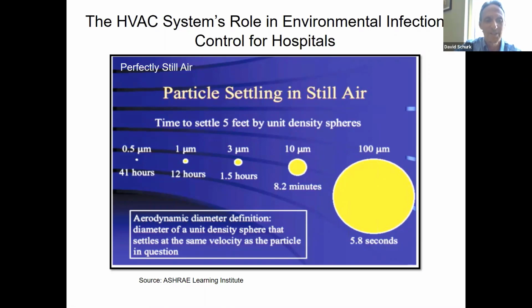Let's take a hospital room, for example, right? You've got a patient in the room. They're moving around, they're rolling in the bed, they're getting up and going to the restroom, whatever the case might be. You've got healthcare professionals coming in and out of the space, creating air currents on a regular basis, maybe dragging things with them as they leave. You have an HVAC system that, for example, may be pushing air into or pulling air out of the space. All of that is creating relatively considerable turbulence within that space. And the point is simply this: as the turbulence is increased, these settling times become extended exponentially.